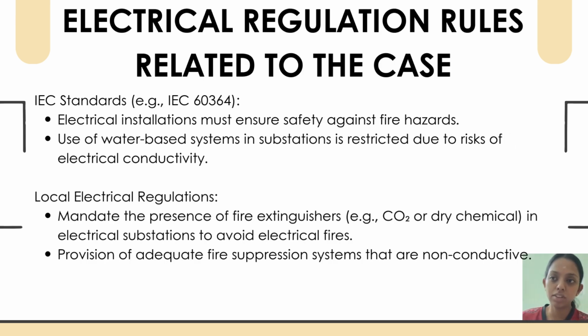For the electrical regulation rules related to the case, it's based on IEC standards. Electrical installations must ensure safety against fire hazards. Use of water-based systems in substations is restricted due to the high risk of electricity conductivity. Local electrical regulations mandate the presence of fire extinguishing agents, for example CO2 or dry chemical, in electrical substations to avoid electrical fires, through provision of adequate fire suppression systems that are non-conductive.